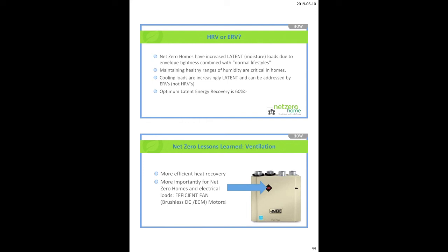But by going to ECM motors, it's a 2 GJ reduction. So again, we're going to say get your efficiency up, 65, 75, that's good. Get to an ERV. Next, before you go any higher on efficiency, get to an ECM motor, and then the last step is to go out and find that world-class 90%. But it's the motors that become sort of the low-hanging fruit.